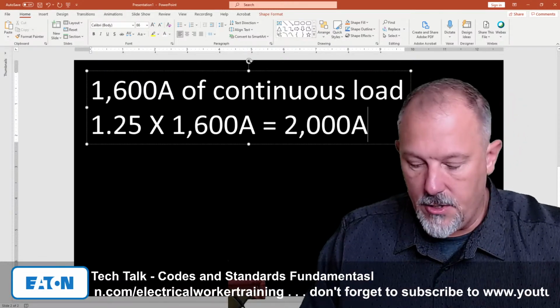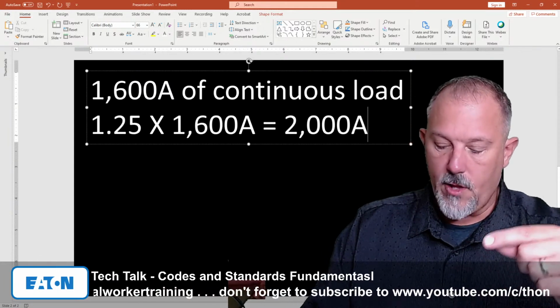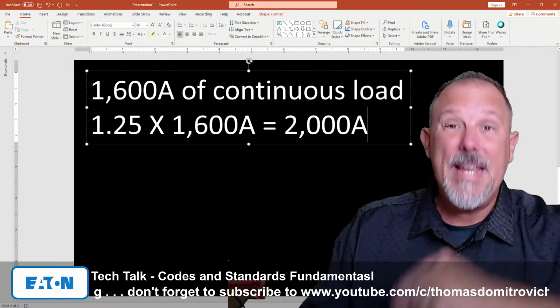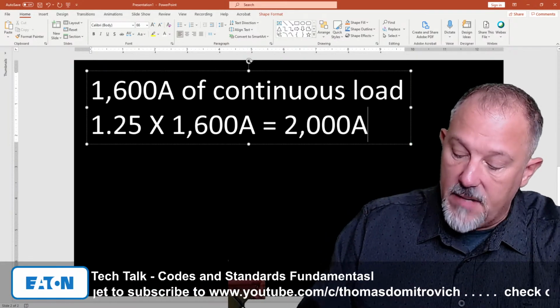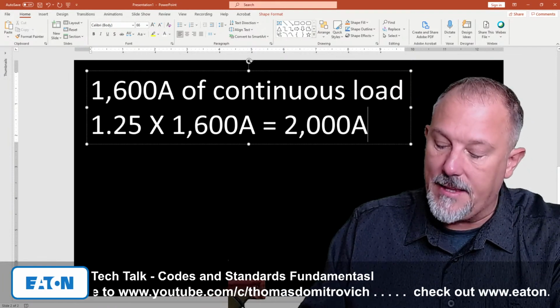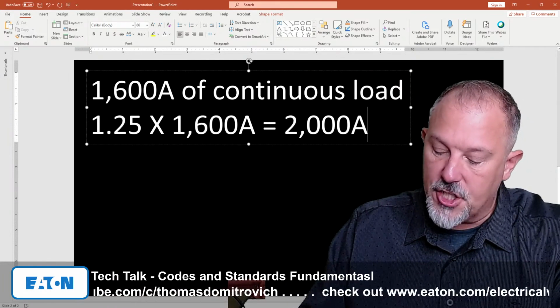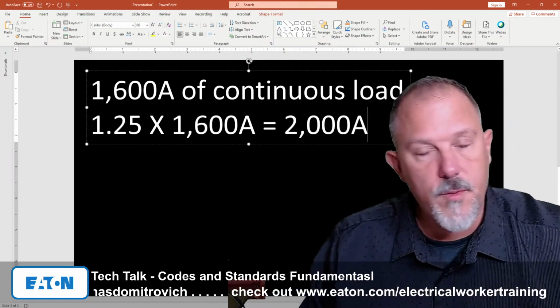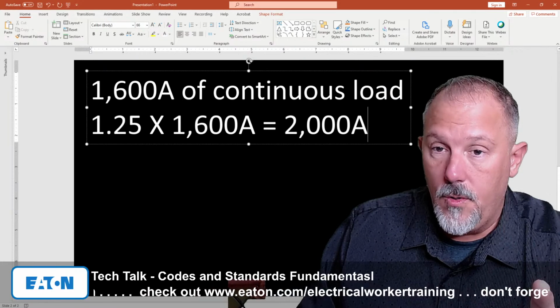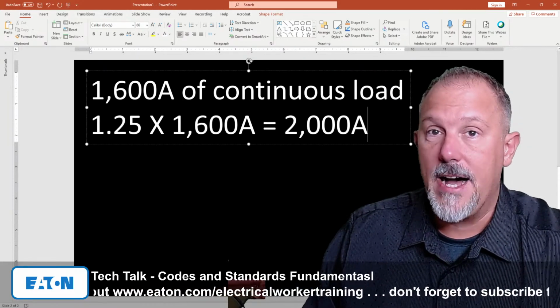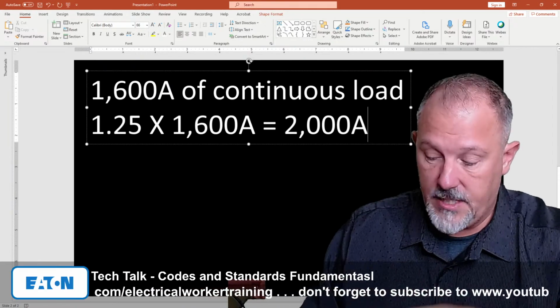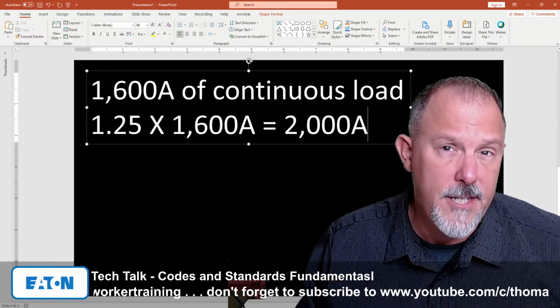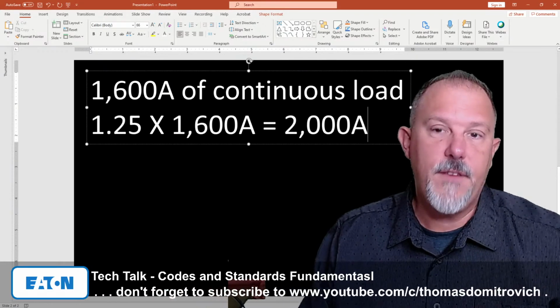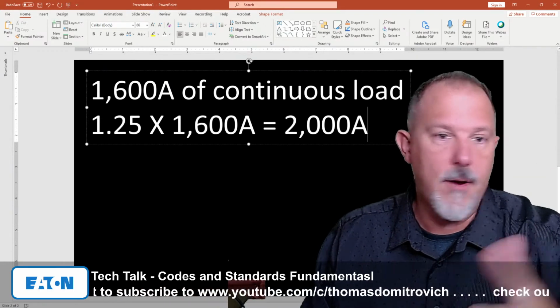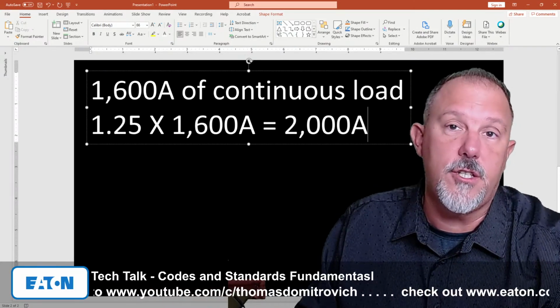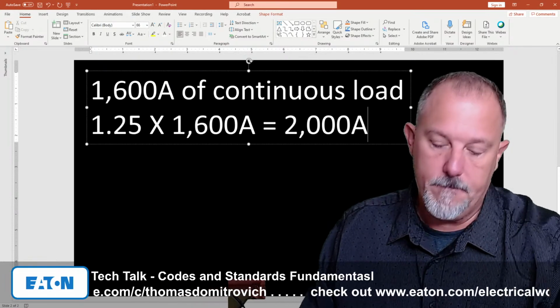And then as part of 210.19(A)(1)(b), the minimum branch circuit conductor size shall have an ampacity not less than the maximum load to be served after the application of any adjustment or correction factors in accordance with 310.15. So I would not be applying the 1.25. I would just apply the ambient temperature correction factors and the conditions of use factors and figure out what ampacity value I would come out with there. I can't do the calculation here because I don't have the conditions of use. I've not established that.